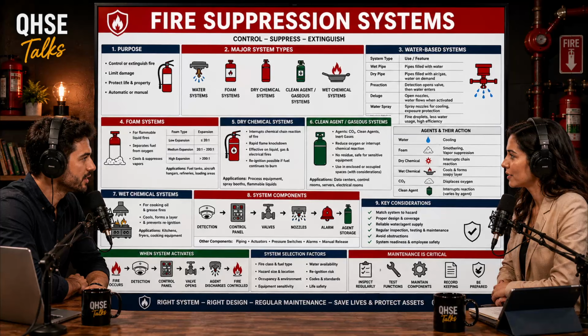That's brilliant. What's the functional difference between low expansion and high expansion foam? Low expansion foam has a relatively dense, wet consistency. It expands maybe 10 to 20 times its volume. Because it's heavy, it's excellent for shooting out of a high-pressure nozzle across a long distance, like at an airport.